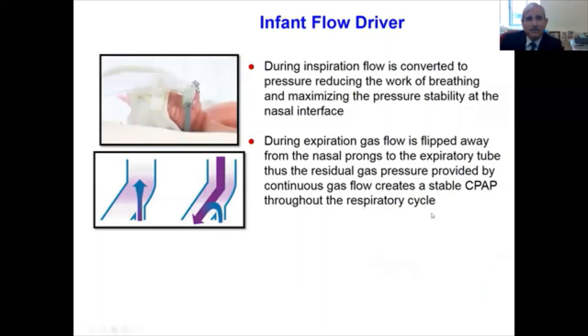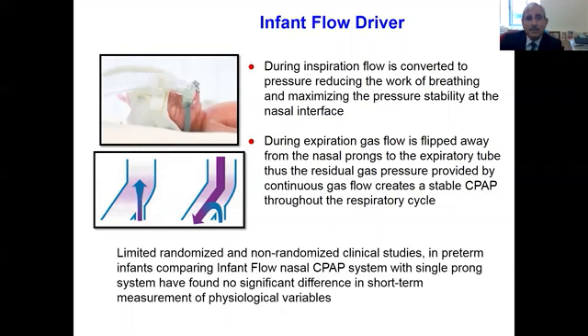To illustrate further: in the variable flow Infant Flow Driver, during inspiration the flow is converted to pressure, which reduces the work of breathing and maximizes pressure stability at the nasal interface. However, during expiration the flow is flipped away from the nasal prongs to the expiratory tube. The residual gas pressure provided by the continuous gas flow creates a stable CPAP pressure throughout the whole respiratory cycle.